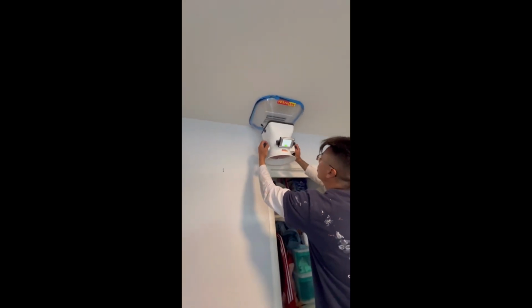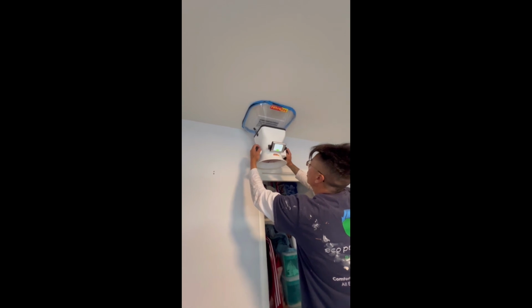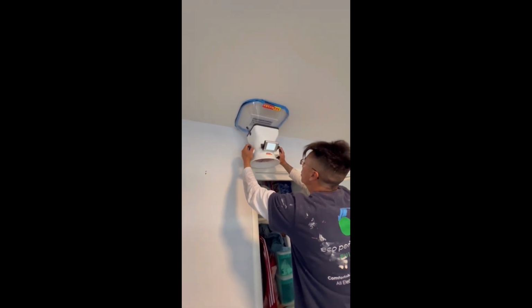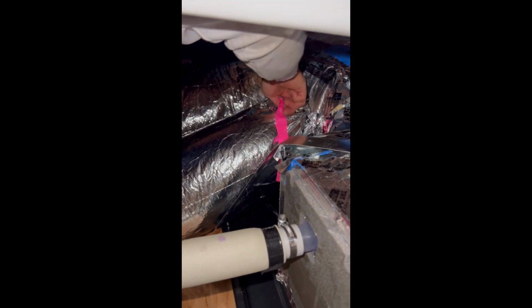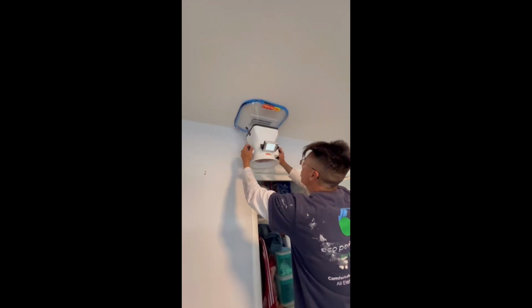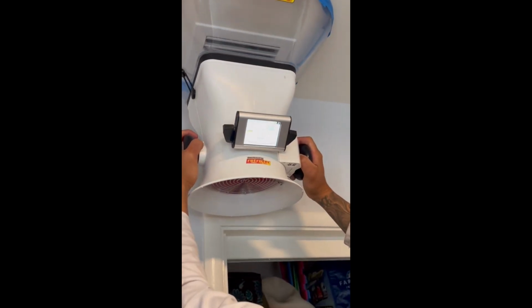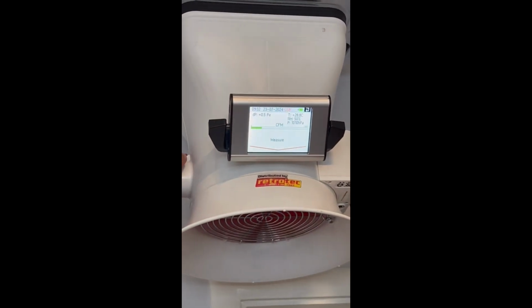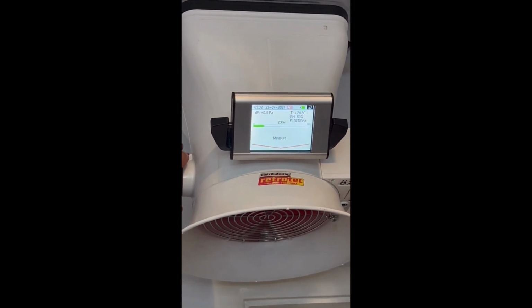Now we're air balancing, so we're using a digital powered flow hood to make sure that the air flow is to the precision that we wanted from the design. And then this is the person in the attic adjusting it, and then we're getting our actual true airflow at the end, so we know we hit our mark. So we have even temperature throughout the home.